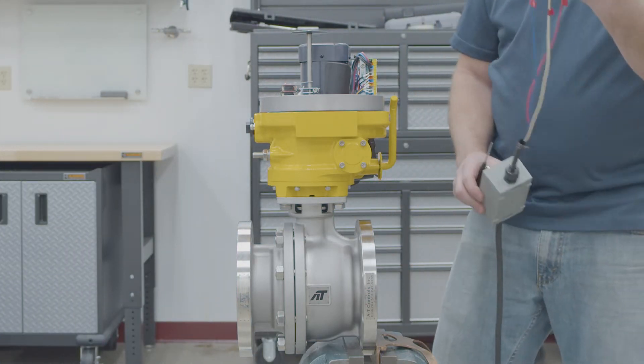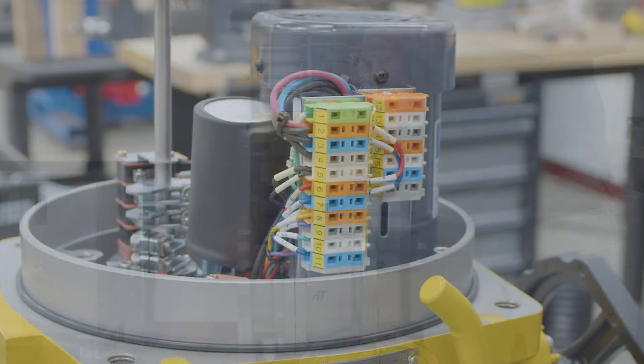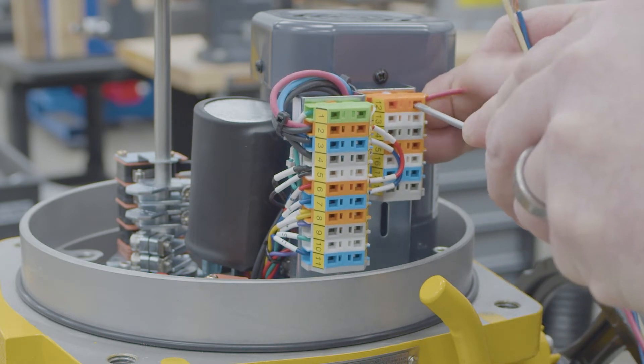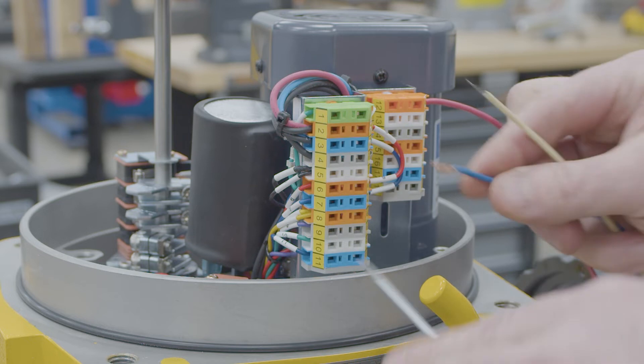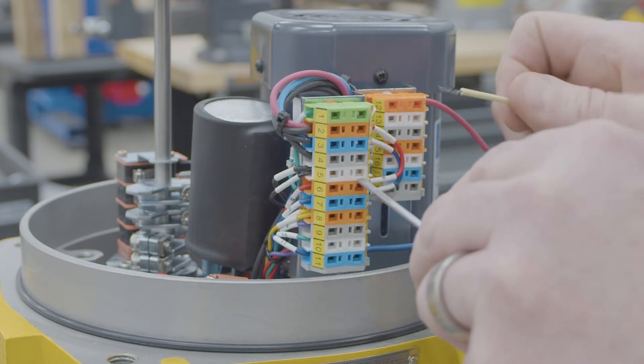All right, this actuator is 110, so we have a 110-volt switch box. So to actually wire the actuator and power it, 12 is going to be your clockwise or your closed position. 11 will be your counterclockwise or your open position, and 5 will be your neutral.